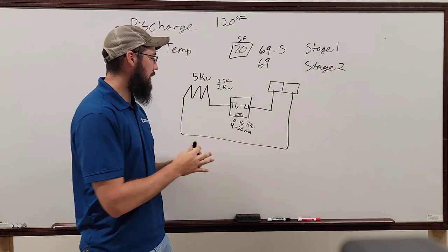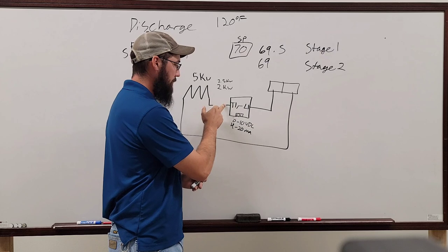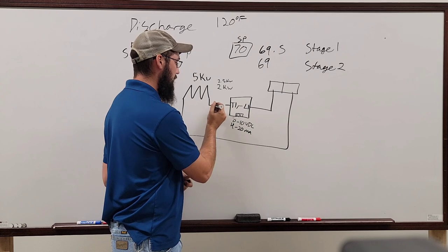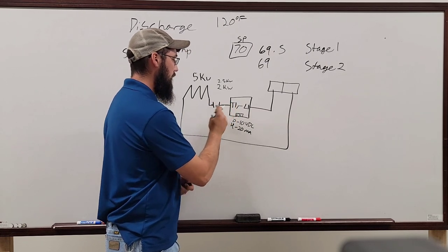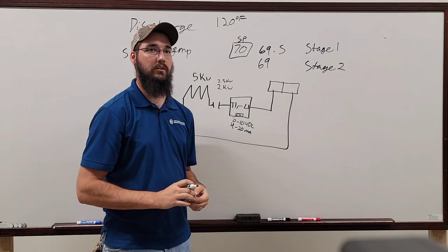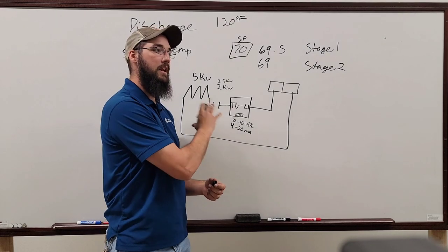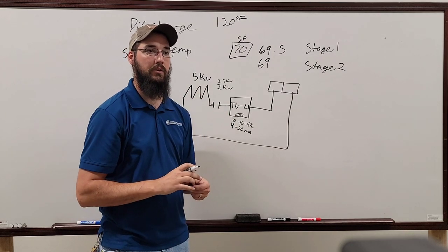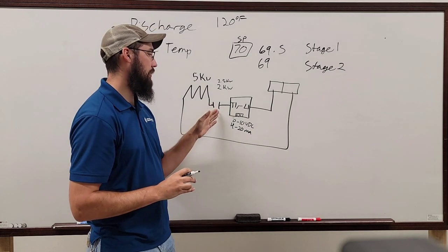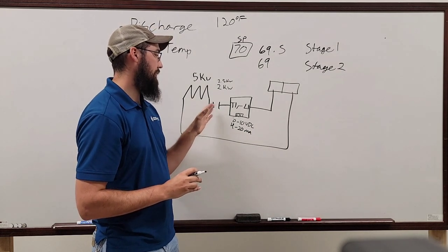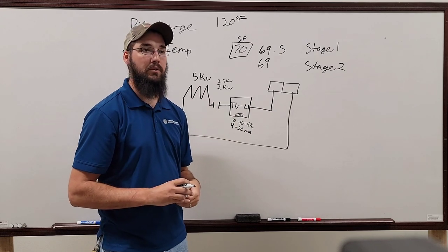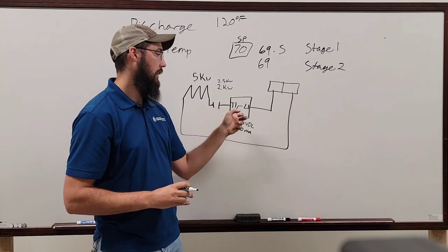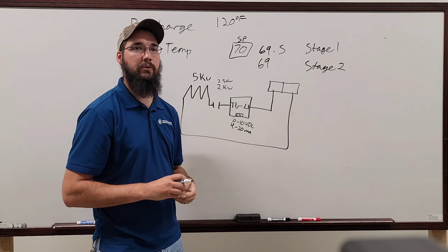So another thing, I don't want to confuse you: many times, and this will be after the SCR typically, they will have a contactor. Okay? This is a safety interlock. So just keep that in mind. And usually all three legs will run through it, or both legs, just depending on the scenario. If one of the pilot duty safeties trip, it'll open that contactor, and the SCR will be outputting, but obviously it won't be going through.